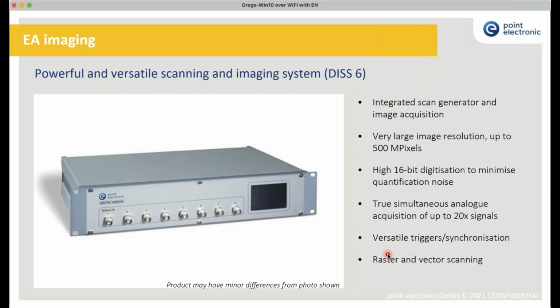Another unit that completes the system is a scanner. It's generation 6, and this is the most powerful scanning system we've ever made. This is the one that will connect to the external scanner of the interface in the same way that EDS or EELS and other TEM techniques do. It will generate a scan, it will tell the beam where to be and where to go, and it's also digitizing all the signals, and we're digitizing at quite a high bit dynamic range, 16 bits, in order to retain the best signal we can for electrical analysis.